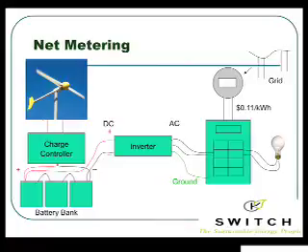So you get this DC power in here, it's going into your batteries, it's controlling your batteries. That's what the charge controller does. It allows it to fill. If it gets depleted, your inverter pulls it off, turns that into really clean AC that you can't tell the difference between this and the Darlington nuclear power, and it goes into your panel. So in that case, the power can go here and supply your loads. That means you have to pull less down off the grid. So essentially your bill goes down. You don't know really how much because there's no meter on it, but you get less of a bill.